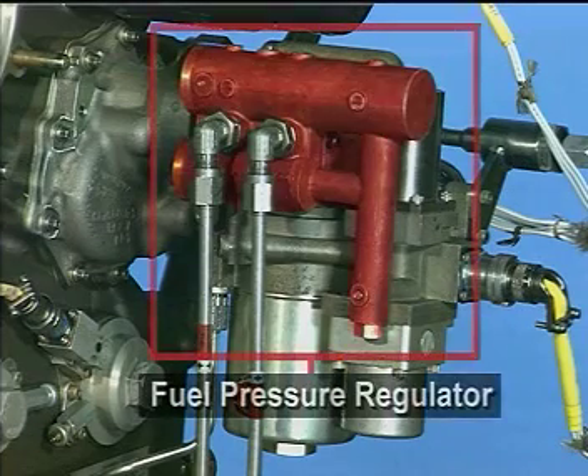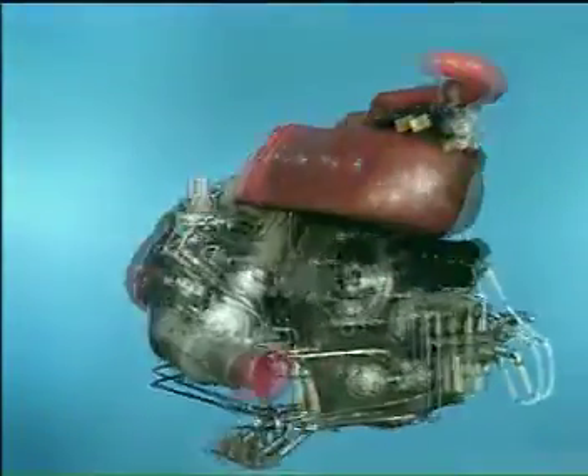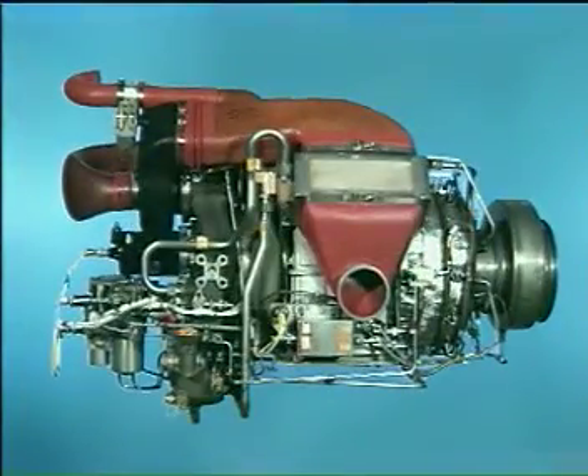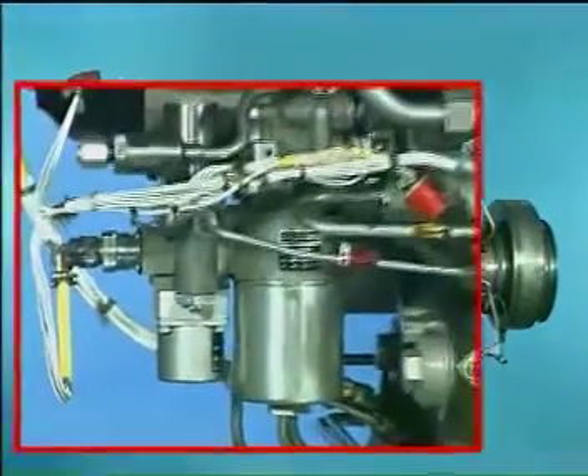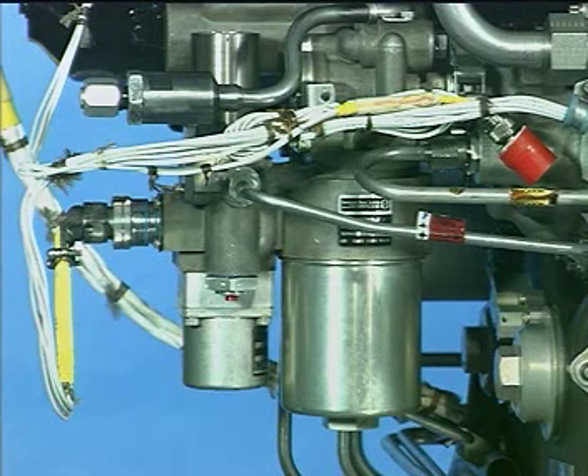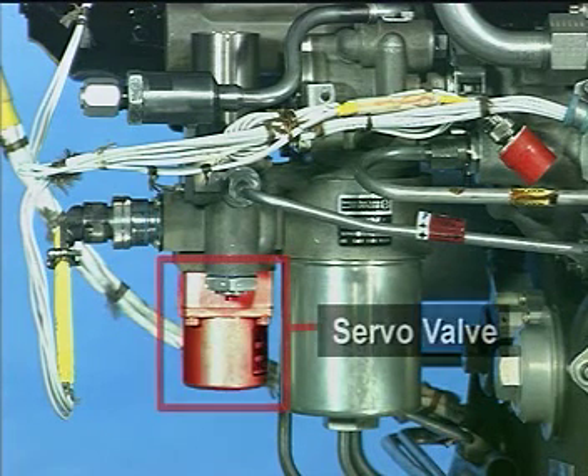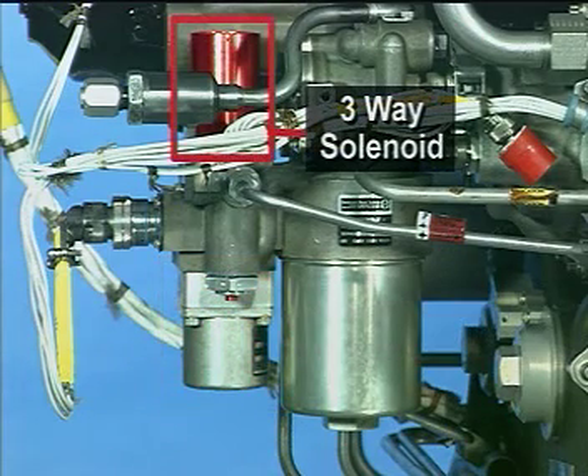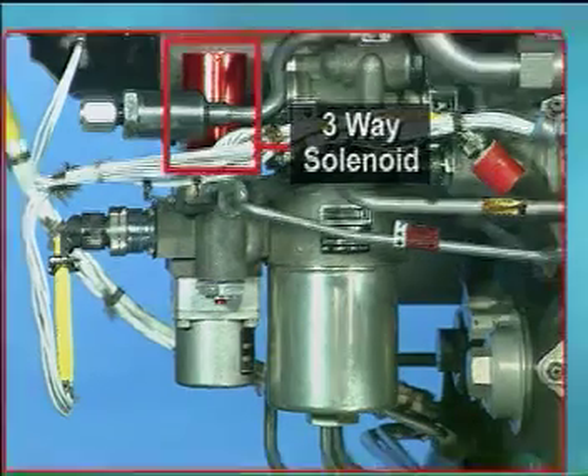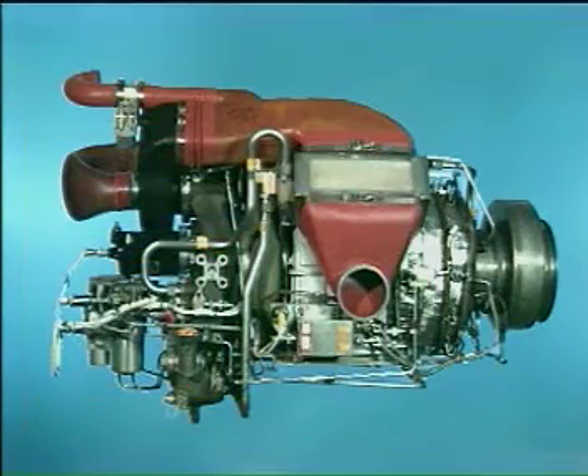The fuel pressure regulator supplies servo fuel to operate the inlet guide vane actuator and the bleed control valve. The fuel control unit servo valve regulates the fuel flow to the power section. The fuel flow is controlled by the three-way solenoid valve. The servo valve and the three-way solenoid valve are controlled by the electronic control box.